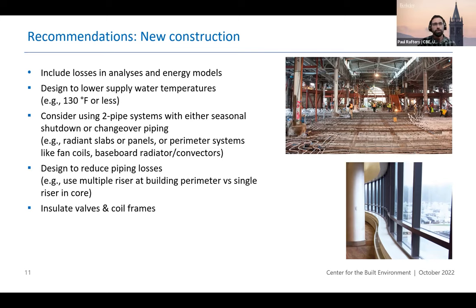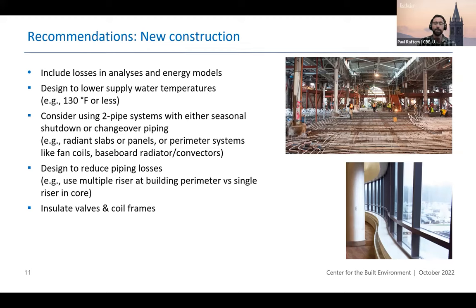There are other things you can do as a designer or advocate for as an owner. For example, considering two-pipe systems with seasonal shutdown or changeover piping means that the losses happen within the envelope at the right time of year so they have a minimal effect. Right now, losses are generally happening throughout the year — even in summer you pay for it twice: you pay for the heat to heat up the hot water that gets lost in the building, and then you pay for chilled water and electricity consumption to reject that heat. Two-pipe systems allow that to happen more naturally. You can also design to reduce piping losses by minimizing the amount of piping using multiple risers instead of a single riser and floor-level distribution on every single floor.